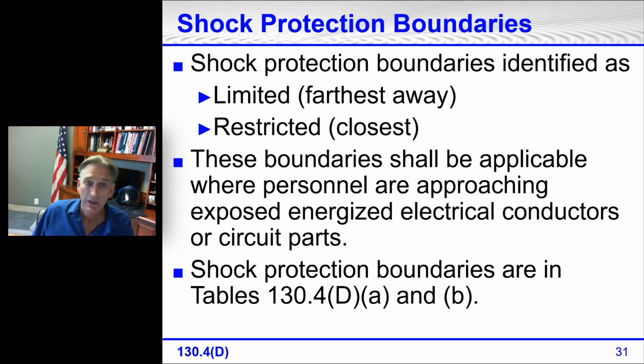the glove is going to be exposed. With shock, we have two boundaries. We have a limited approach boundary, which is the farthest. We have a restricted approach boundary, which is the closest. These boundaries are applicable where personnel are approaching exposed energized electrical conductors and circuit parts. Shock boundaries are in Table 130.4(D), (A) for AC and (B) for DC. And for shock boundaries, everything except 120 volt is based on phase to phase. And it's really very easy.